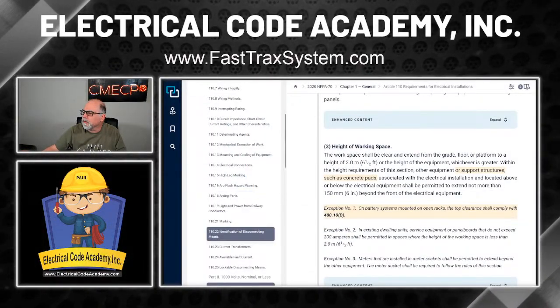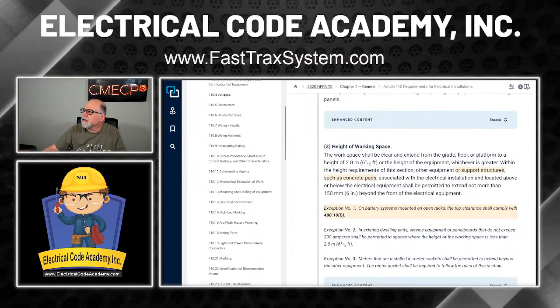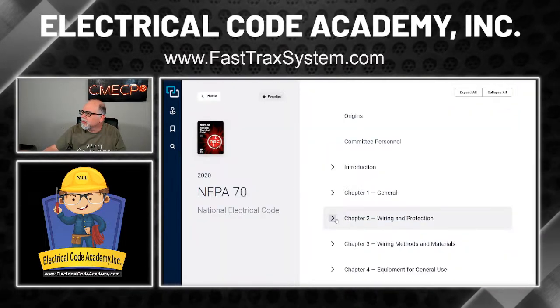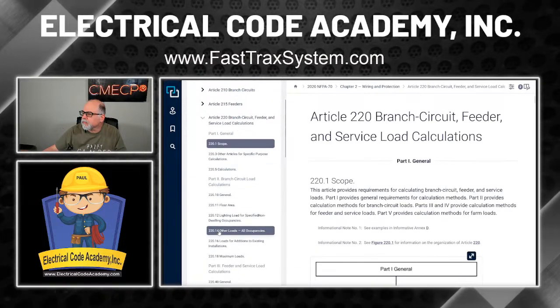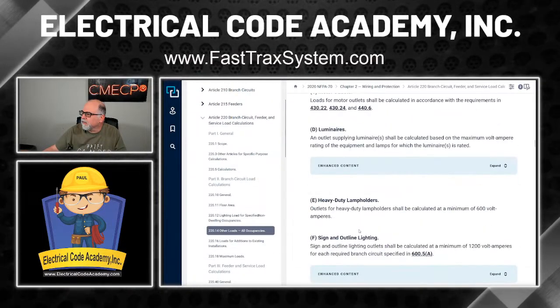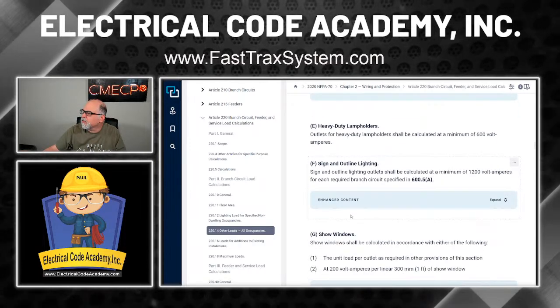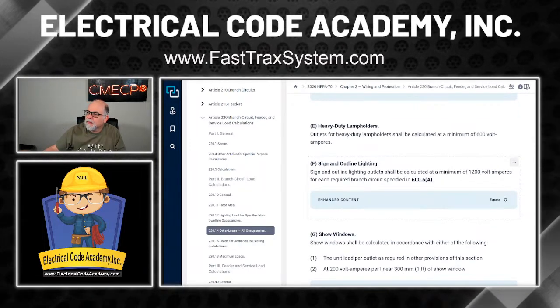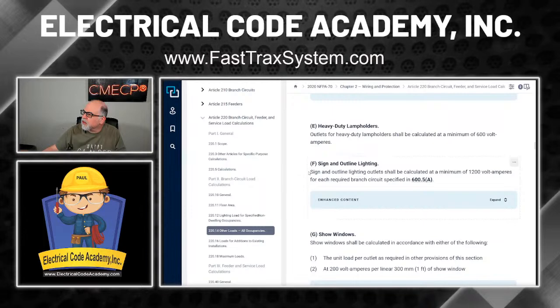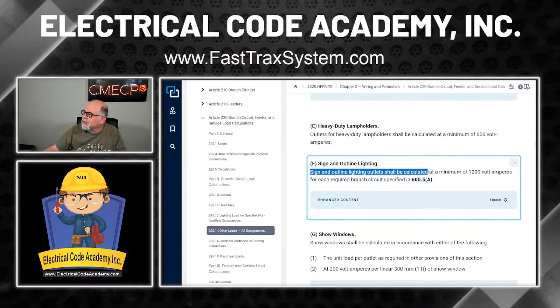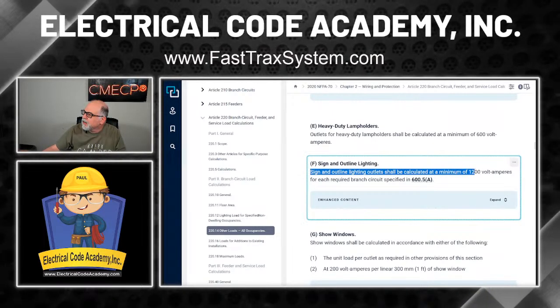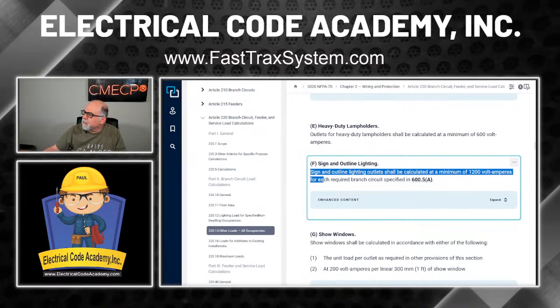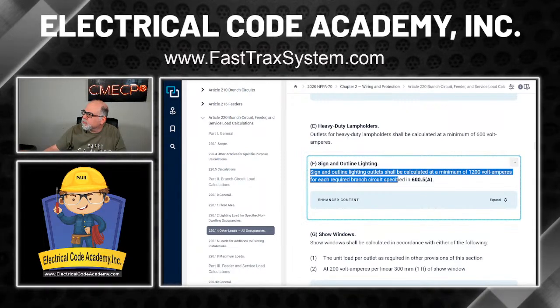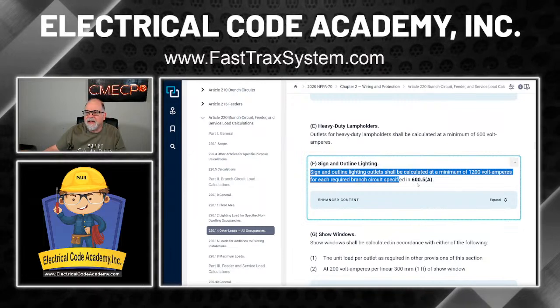And let's see here. Go back to the code here. Let's go to 220.14. Right here. And we've got to go to F. All right, here's F right here. Okay, now it says, sign and outline lighting circuits shall be calculated at a minimum of 1200 volt-amperes for each branch circuit specified in 600.5(A).